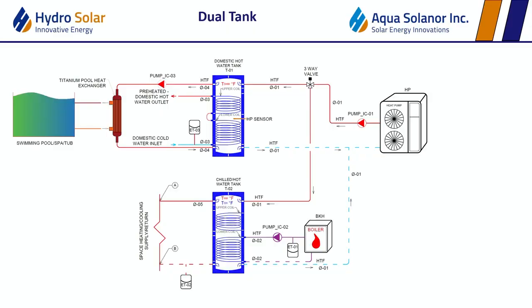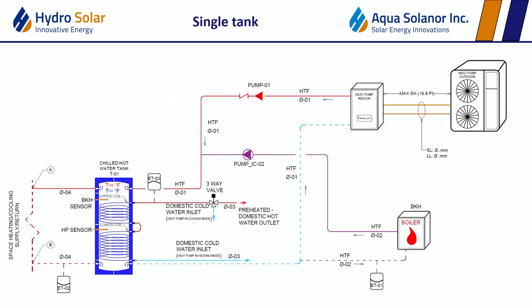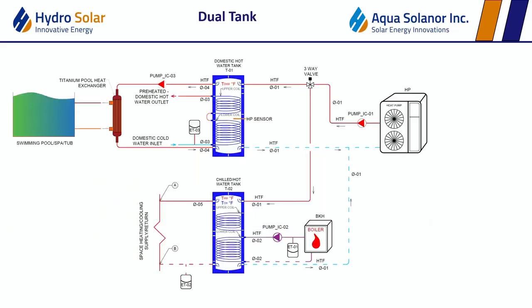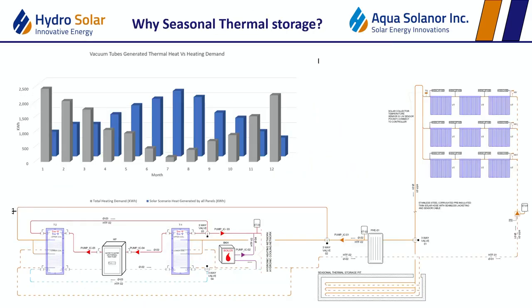Here's another slide. We have an air-to-water system again. We're not yet preheating with solar, but you can see we take one of the tanks, the energy stored in it, and dump it into a pool. This is where it comes into play with conventional systems. Going the other way, you can have solar collectors feeding into an air-to-water or water-to-water system, and that energy gets dumped into a swimming pool or into domestic hot water production. Think of it as a preheat, not as the main source of heating.